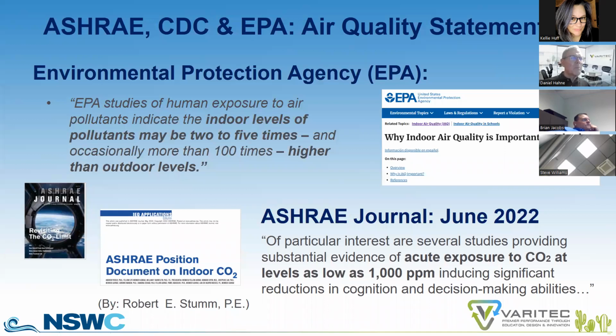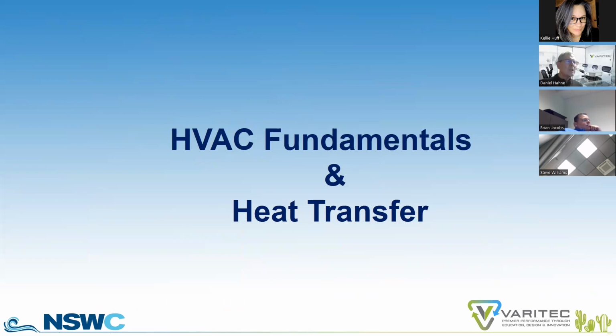designed at 700 parts per million on the inside, not to exceed 700 parts per million more than the outdoor air CO2 levels. In general, outdoors, depending on the location, you could see anywhere from 350 up to 600 and 700 parts per million of outside air. So consequently, if you add the 700 parts per million buffer, as proposed by 62.1, you could easily have an indoor environment of 1,200, 1,300 parts per million. So this is an ongoing discussion that I want to bring to your attention because it does invite the question that maybe more outside air makes all the sense in the world to help control CO2 levels.